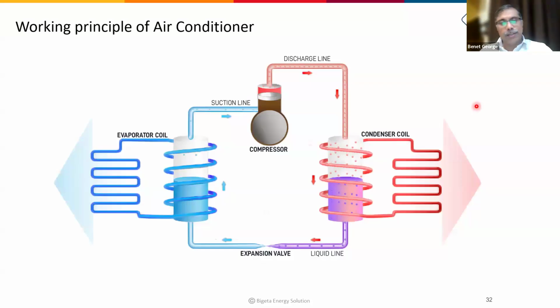It's a closed loop system. We have a compressor. The compressor will compress the refrigerant. Whenever the compression happens, the temperature will increase. That will go to a condenser. In this case, it is a water-cooled condenser, which is why you can see the coil there. That heat will transfer to the water and it will finally go to the cooling tower and be discharged to the atmosphere.